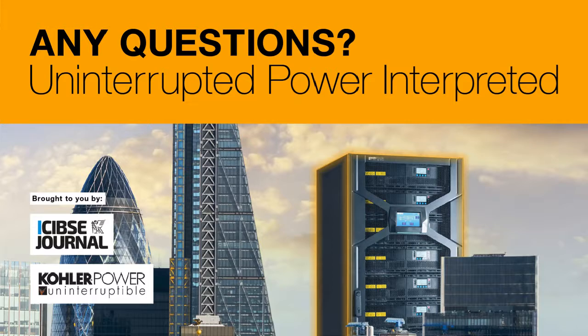A question here. I think it's concerning demand side response. It refers to DSR, so I presume that's demand side response. Is it feasible to consider UPS as battery storage for demand side response schemes at this stage? Yes, it is possible, and we've talked about this, but we have to make sure that we know what we're doing. The battery has to be a different type of battery. A typical UPS battery is a standby battery, not a cyclic battery. So we'd have to take that into consideration if someone wanted that. But demand side response can be done with any UPS. When you need to run off the storage battery, you disconnect the input supply and let it run. Okay, thank you very much.